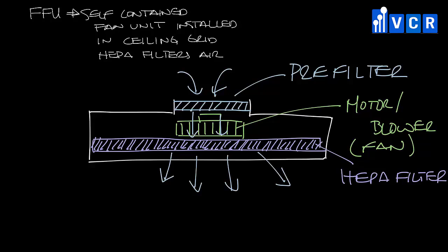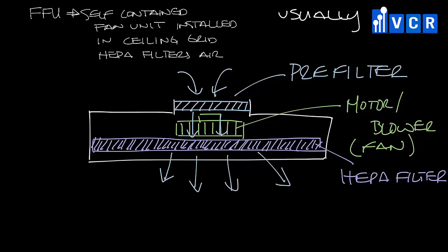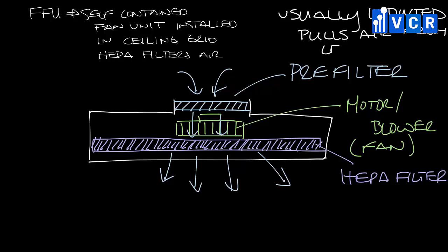You can get an inlet that you can duct to on a fan filter unit, but often they are unducted and they just pull air from the ceiling plenum. So an air handler would put conditioned air into the ceiling plenum, and then the fan filter unit would pull it out and filter it before it goes to the space.